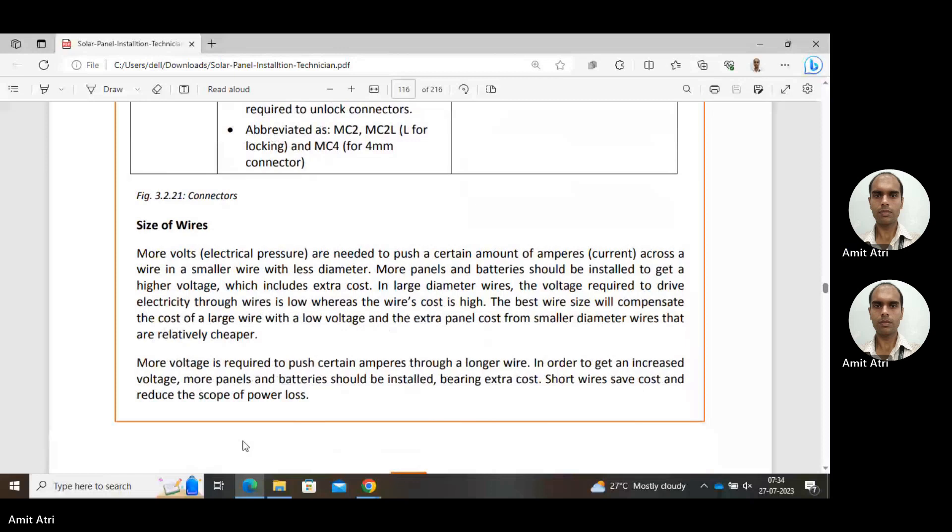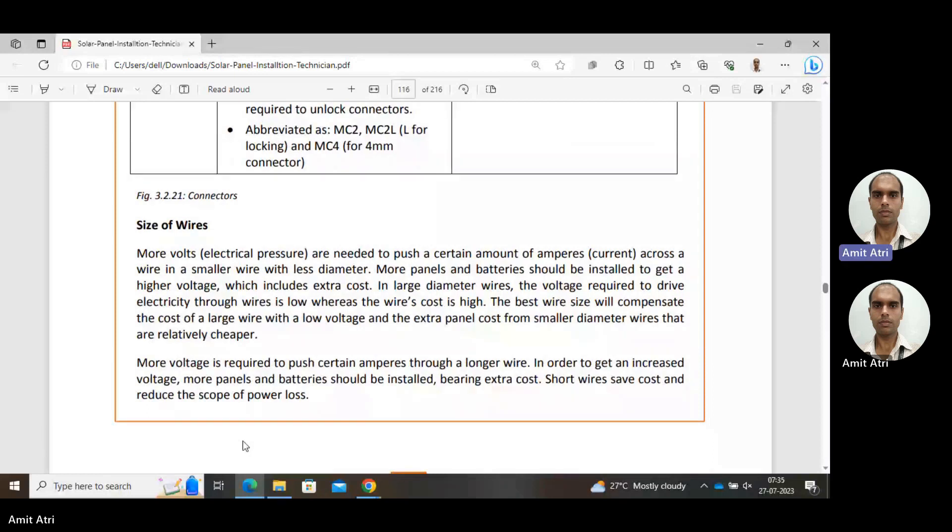Larger diameter means more metal is needed and correspondingly the cost increases, but resistance is less so voltage required will be less compared with a thin wire. With thin wire, more voltage is needed so we need to install more panels and batteries. In case we are using a thicker wire with larger diameter, voltage required will be less, meaning fewer panels, but the cost of wiring will increase. The best wire size will compensate the cost of a large wire with low voltage and the extra panel cost from smaller wires that are relatively cheaper.